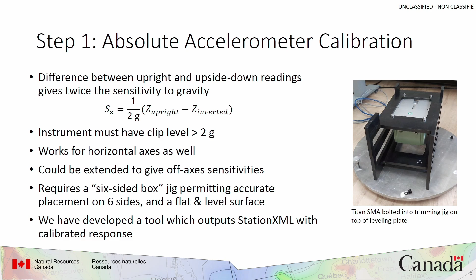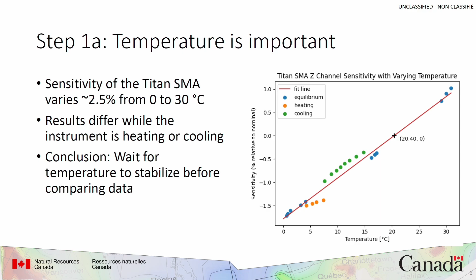So we did that for a bunch of sensors over a couple of days in spring in Canada, where the temperature varied by 20 degrees or 30 degrees. And the accelerometer itself has, not surprisingly, a fairly strong temperature sensitivity. Furthermore, while the instrument is heating or cooling, the errors are larger, so that tells us that it's important to let the temperature stabilize before doing this test.